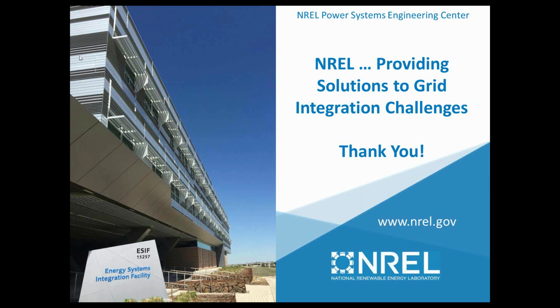Okay, next one. The Sandia report seems to specifically evaluate islanding conditions where the inverters are all using positive feedback-based anti-islanding. Would this not make the final screening steps invalid for non-positive feedback-based anti-islanding? That's a good question. I don't know. Personally, I don't know how many inverter manufacturers are not using the positive feedback anti-islanding techniques. It's a valid question, and I don't know how to answer it without doing some testing on some inverters that don't have the positive feedback. But as far as I know, everybody is using that.